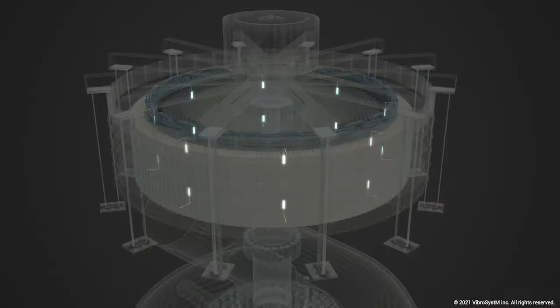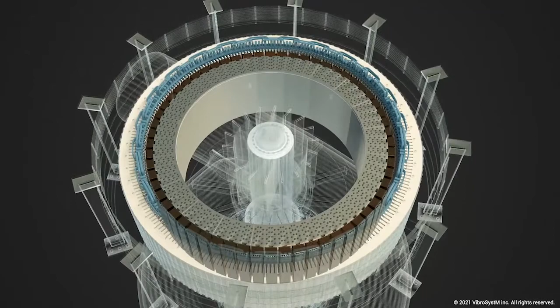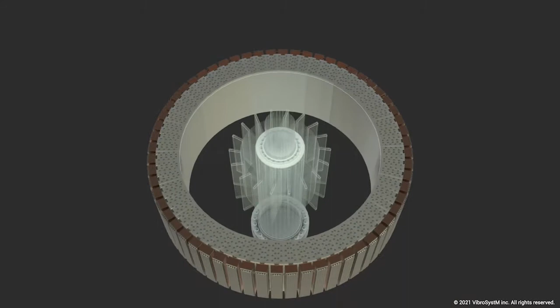When they were ready to begin the commissioning, the utility wanted to do a controlled overspeed test to make sure the rotor performed correctly. Overspeed condition is something that hydro generators can be expected to go through at any time. If they're producing power and for some reason they get disconnected from the grid, they'll go into overspeed, and the OEM has to show that the unit is able to survive this. So they did a controlled overspeed test, and at the same time they wanted to use the results to see if the rotor rim actually performed as the OEM had designed.